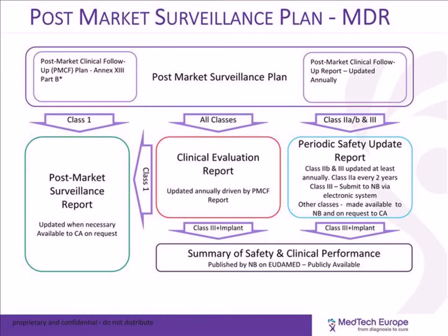So the banner at the top is this post-market surveillance plan that we have reviewed, and it includes the post-market clinical follow-up plan, which is approved by the notified body, and its output, which is the post-market clinical follow-up report. From here, it is distilled in a series of reports whose periodicity is based on the risk classification of the device.